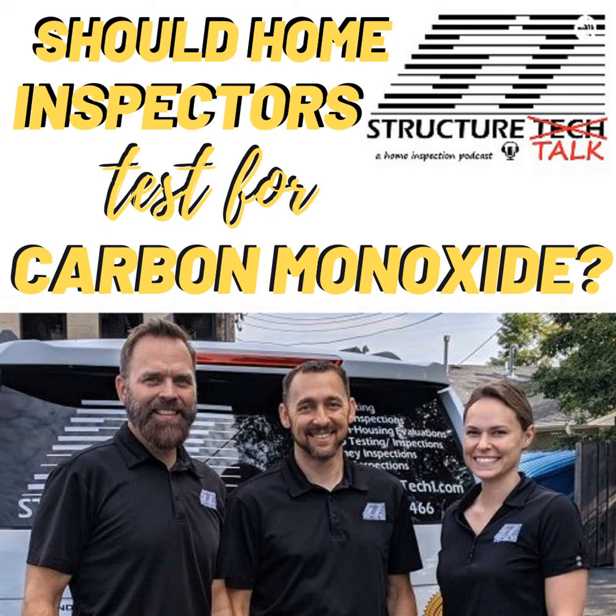And I think we talked in another episode about all the things we do to actually test a furnace. I know we're talking just about CO today, but we talked about doing temperature rise and taking off the panel covers, looking inside for rust or signs of moisture or anything like that, checking the furnace filter. We do all those things. So we talk about that in training too, but then we talk about the proper location to do a CO test and when you should do a CO test. It's very important that you do it at the correct time.